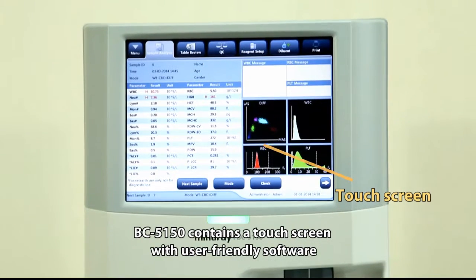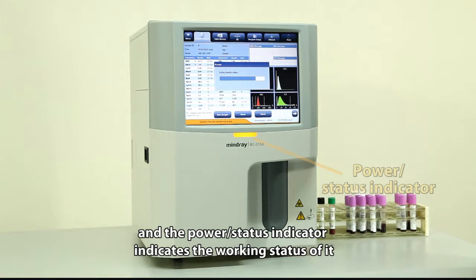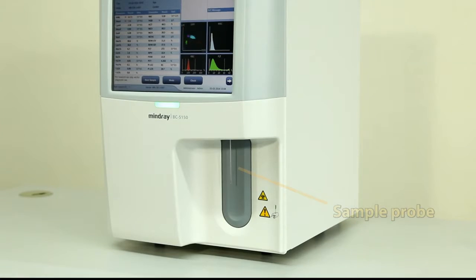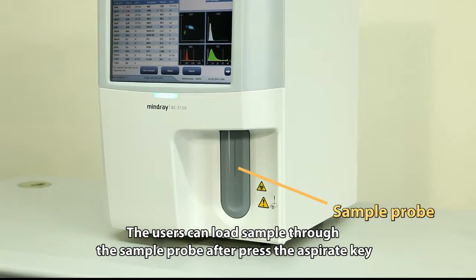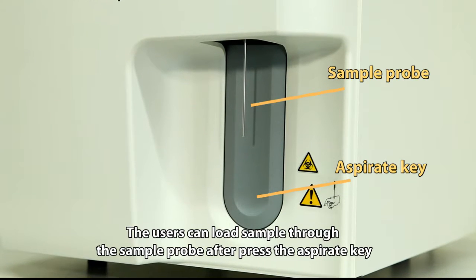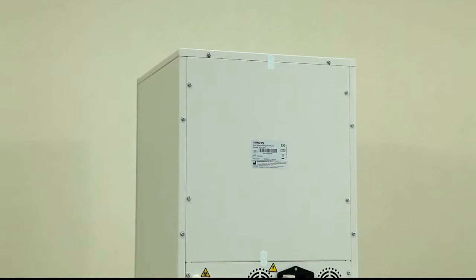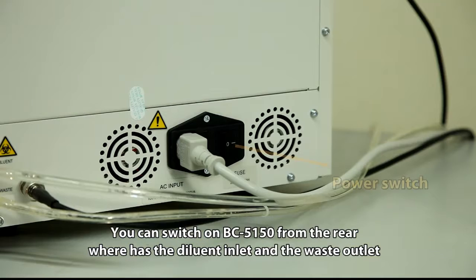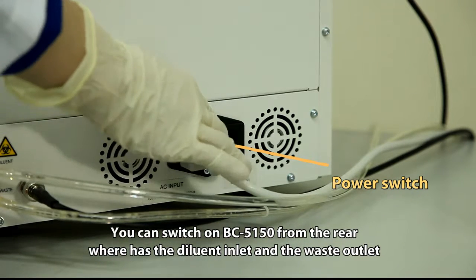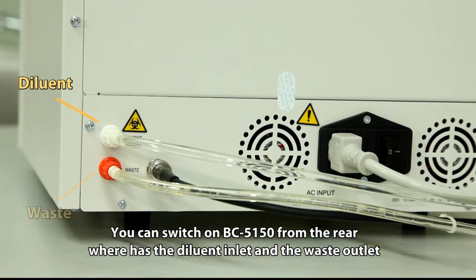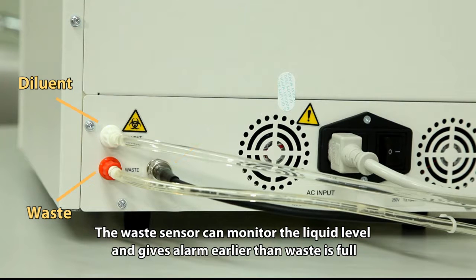BC5150 contains a touchscreen with user-friendly software, and the power status indicator indicates the working status of it. The users can load sample through the sample probe after pressing the aspirate key. You can switch on BC5150 from the rear, where there are the diluent inlet and the waste outlet. The waste sensor can monitor the liquid level and gives an alarm earlier than the waste is full.